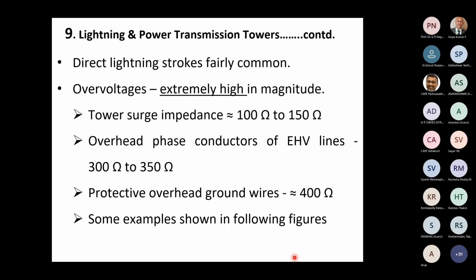Now, let us see the order of voltages that can get generated on transmission lines. Direct lightning strokes are very common. Overvoltages due to these lightning strokes are extremely high in magnitude. The main point to be considered is that the tower behaves as a short transmission line. From top to bottom, it behaves as a very short transmission line. Therefore, we don't have to consider its resistance, or even skin effect resistance or inductance. Equivalently, we can use the parameter, its surge impedance.